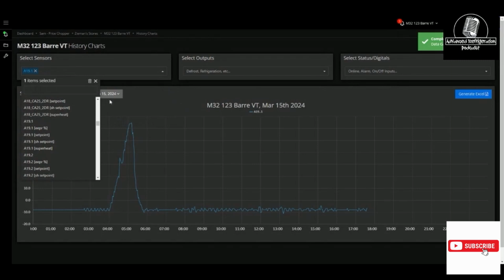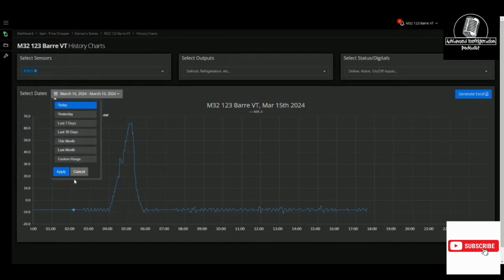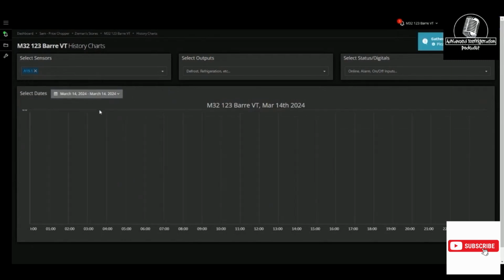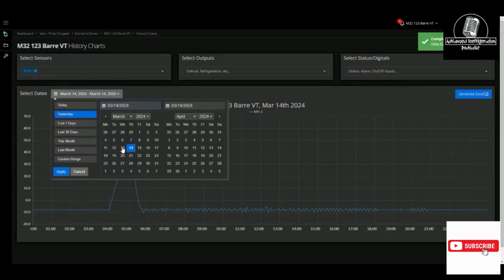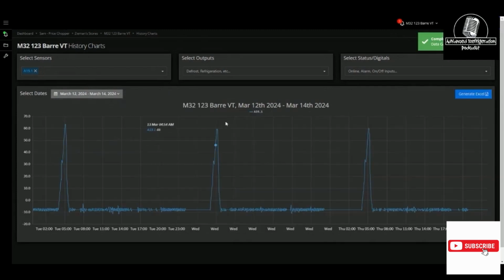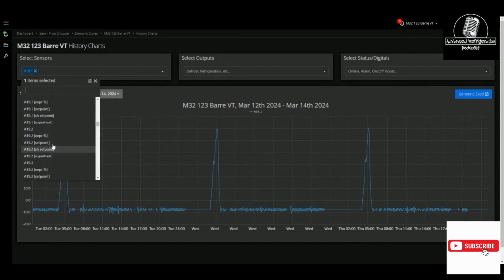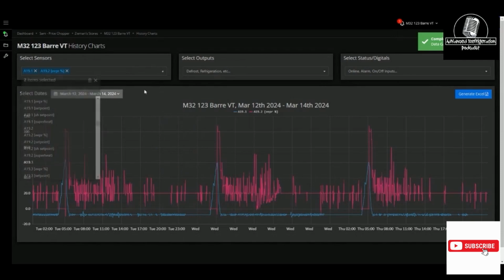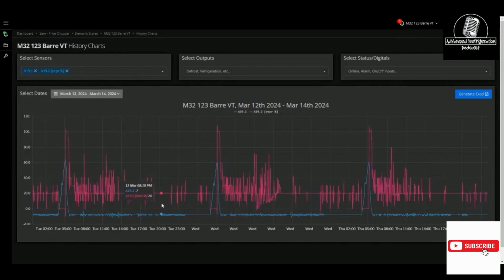So this is like the temperature on circuit 19.1. We'll just say over, actually, let's just go over a couple days because obviously a whole week, right? So this is a low temp circuit. And then if I want to overlay the valve percentage, so it's a pulse valve. So now I can overlay the EPR opening percentage versus the temperature.